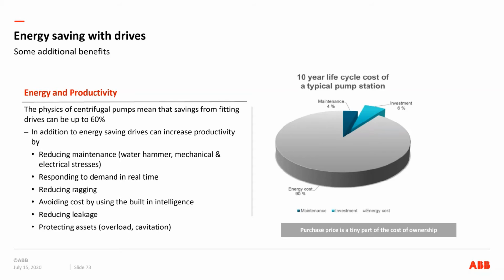So if I can make a 10% energy savings, and I give you 10% off of the drive or 10% off of the pump, I'm only saving you a little bit. If I can save 10% of your energy, I'm making almost a 10% cost reduction over its 10-year life. And that is the biggest savings you have here. There are also other advantages, and I think we've all led to this: less mechanical wear and tear.